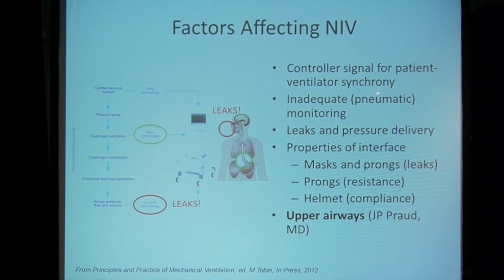So that's one of the factors that affects the delivery of non-invasive ventilation and patient-ventilator synchrony. The other thing is we have very inadequate monitoring with the conventional pneumatics. If you are measuring tidal volume at the airway and you have leaks, it's an unreliable signal. But now we have this neural signal that can tell us whether or not we're being efficient in the way we deliver the assist. Of course, if you also have leaks up here, this will affect your pressure delivery. So even though we have a nice signal for controlling the ventilator, when to start the breath and when to end it, NAVA will still be affected by leaks at the interface because the pressure delivery will be affected by that.